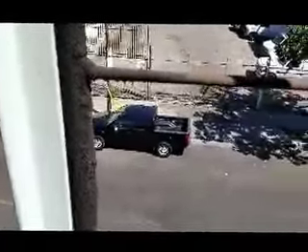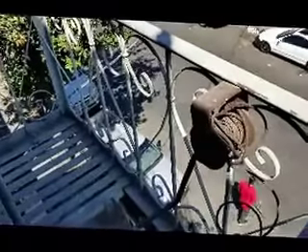Now, there are also some design issues. It's actually sitting outside the platform. It's supposed to be inside. That's a matter to be further discussed. This pre-existing non-conforming issue will be discussed with the AHJ, in this case the LA City Fire Department. As we can see, original hardware all around. Some areas don't even have any bolts, or have missing bolts in some instances, and I'll be documenting that throughout the video.